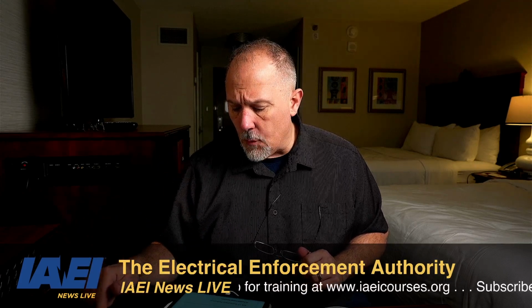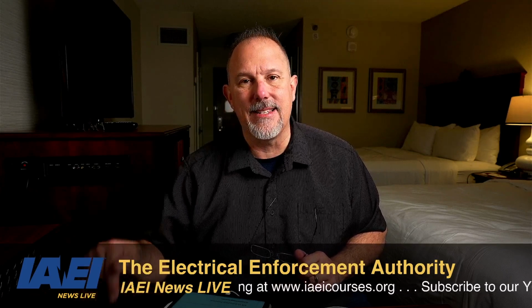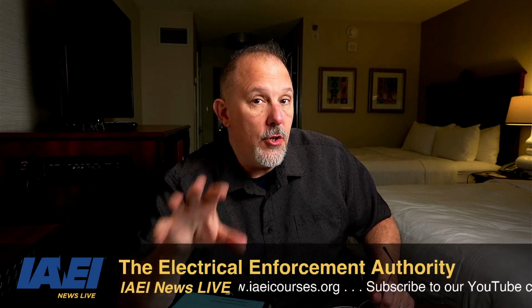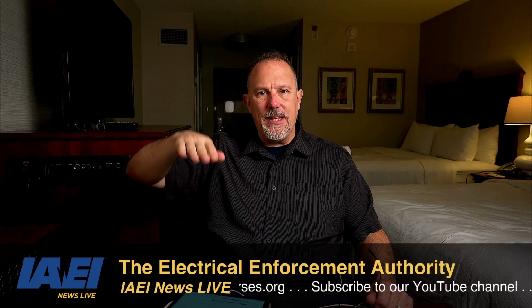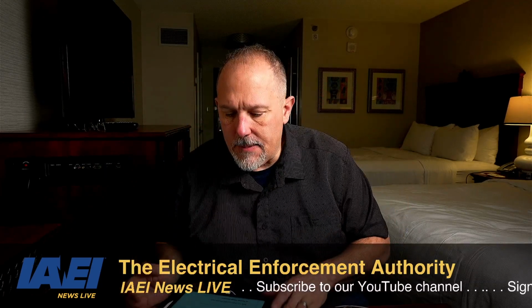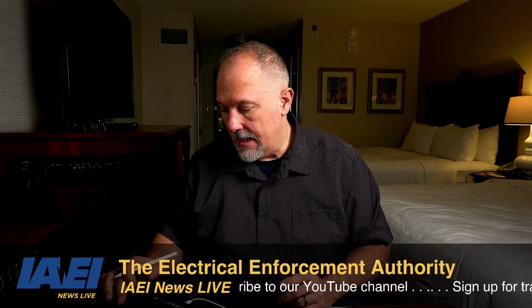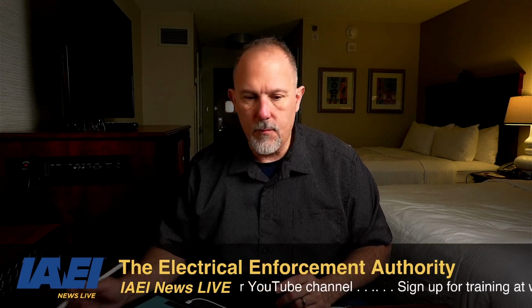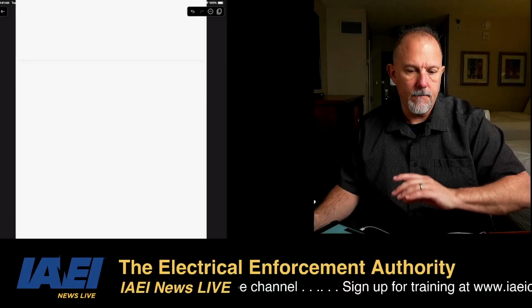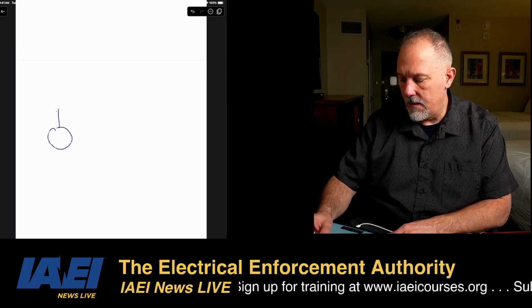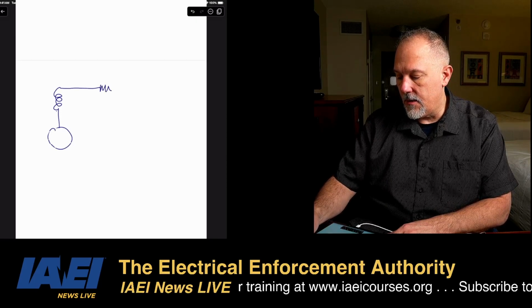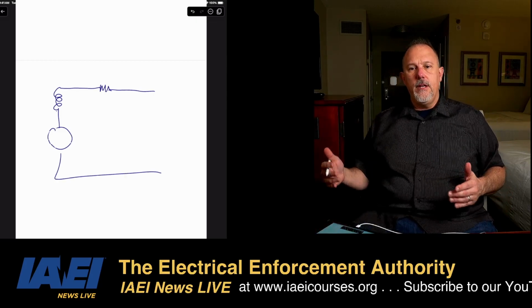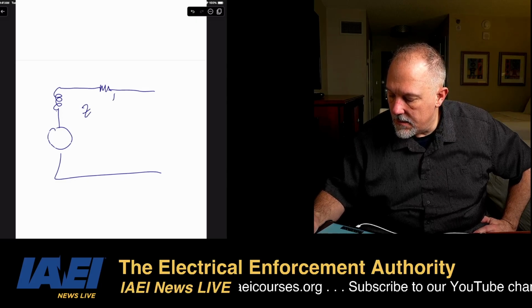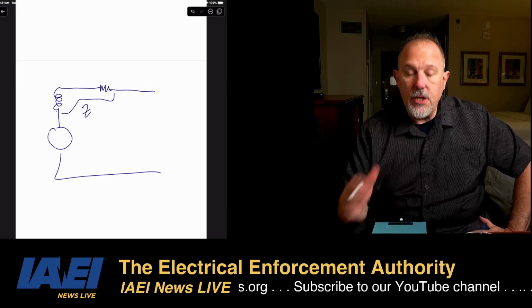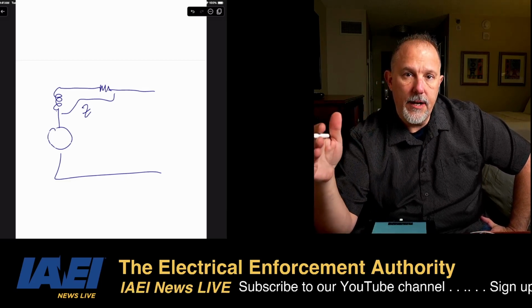Available fault current for inverter-based generators in lieu of the synchronous, subtransient, and transient reactances. Those reactance values are what we use to calculate fault currents at different periods of time. So when you think about how do we model a generator, what you will typically see is a generator, you'll see this, an inductor, and then a resistor as your output. Now, this impedance, this combined impedance, is what we use to calculate fault current on the secondary at the leads of that generator.